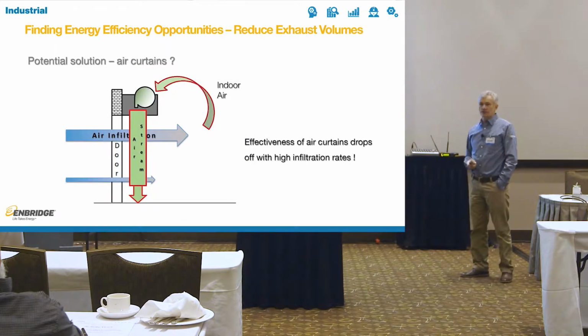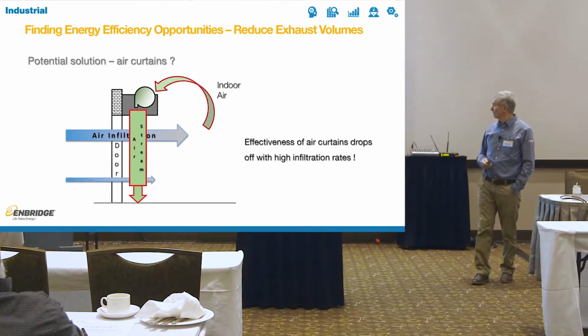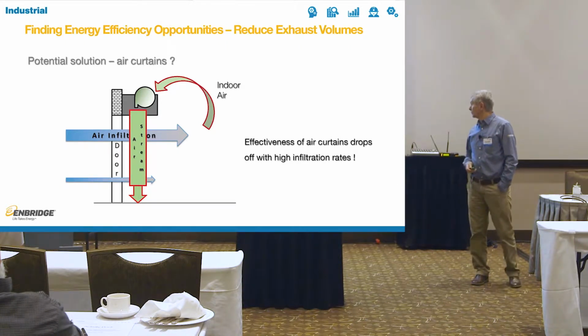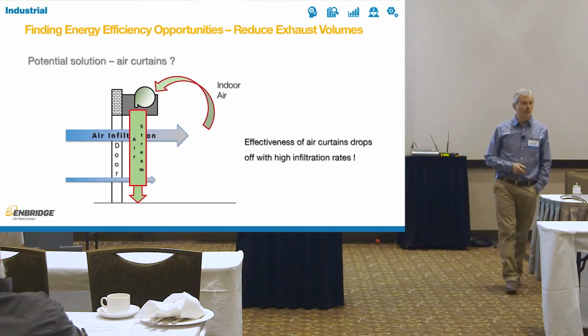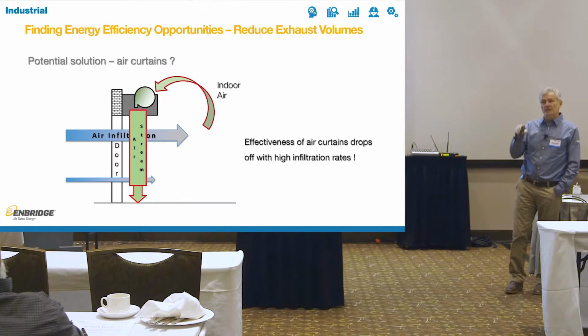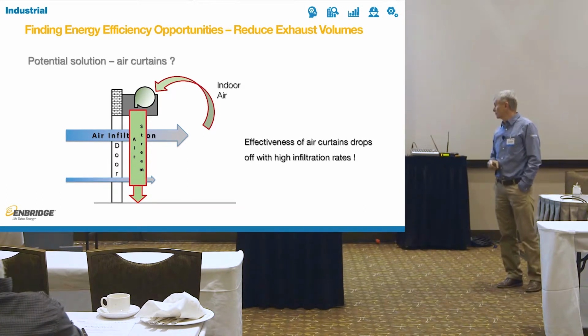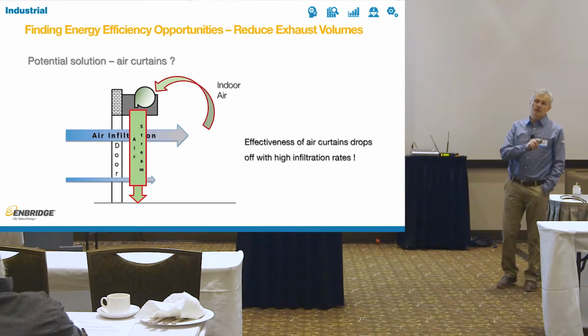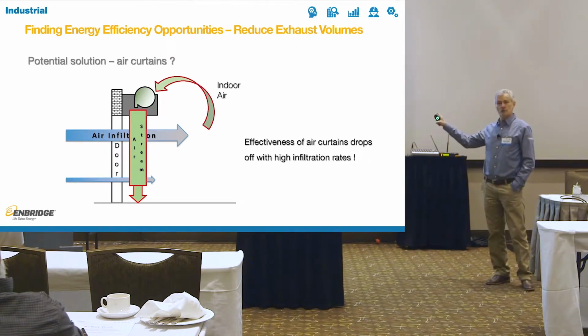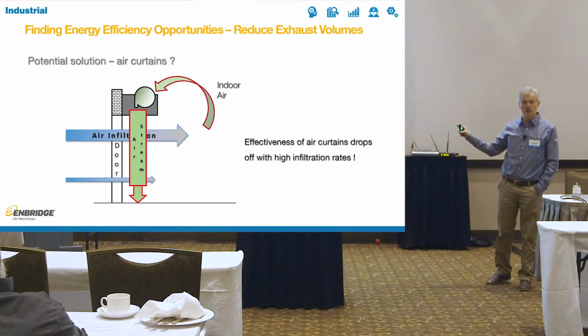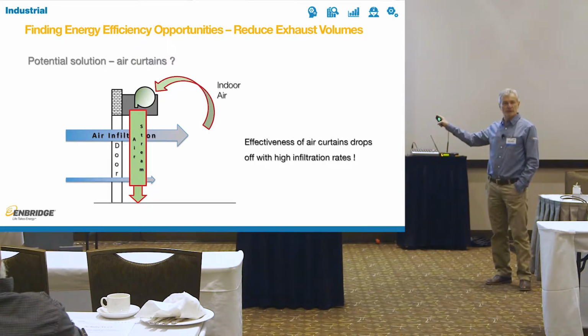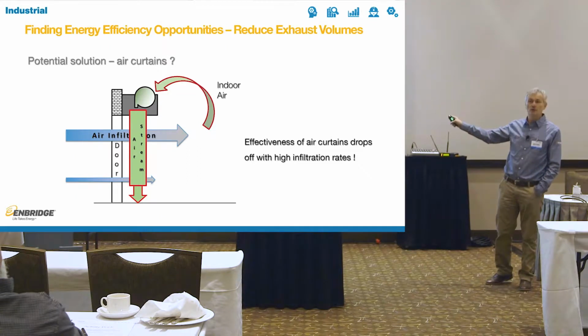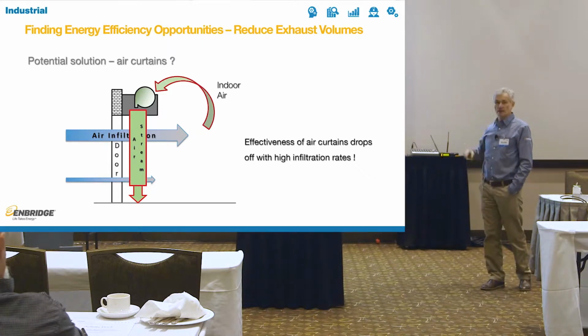Air curtains, another popular solution. You have ambient infiltration. And if you beat it up with the faster air coming from up there, you'll eventually beat that infiltration down and you'll have less infiltration. The problem is the faster this infiltrating air comes through, the less effective the air curtain is. It starts at about 70% effectiveness to begin with. By the time you have any sort of negative balance in the building, you will be at about 25, 30% efficient if you're good. So again, you didn't solve the problem. You spend the money, you didn't solve the problem, and you added electrical load to boot.